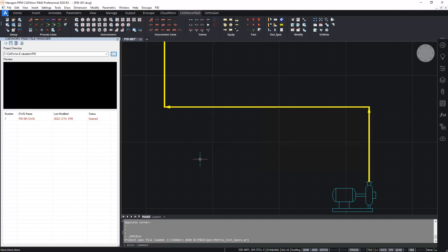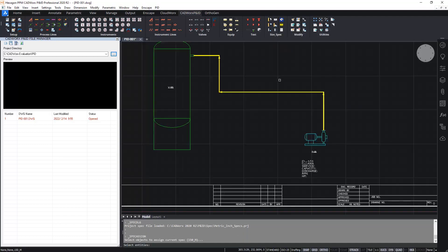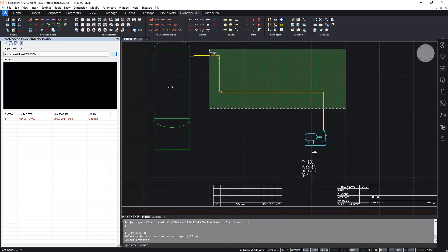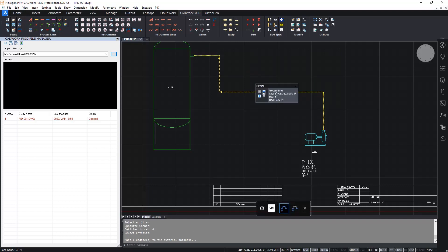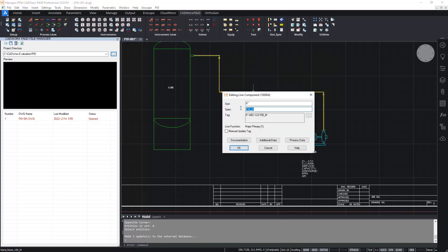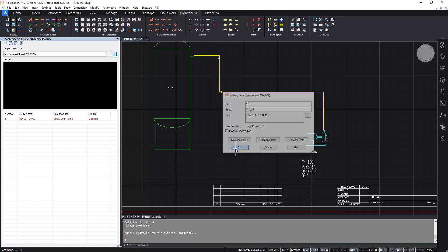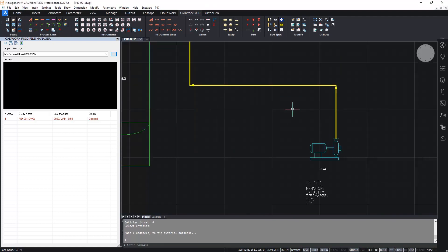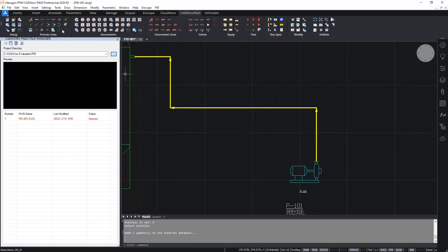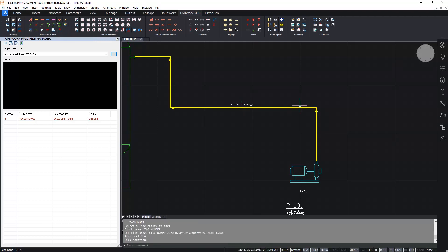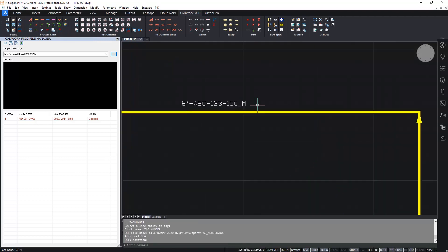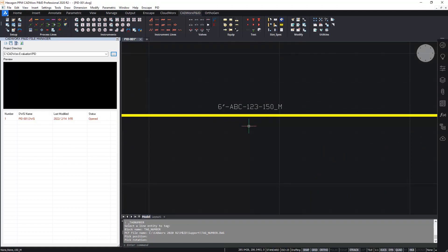Now, once that spec is set, I can then assign that to a selection of components. Of course, I only have the process line, but I'm going to assign that spec to the entire process line. Now, when I double click, we can see the spec has been assigned, the line number, the tag has been completed. And the final thing that I'm going to do here is I'm going to label that, annotate it onto the drawing by using this function here to tag the line and pick the line and select the orientation of the tag. Like so, the tag data is picked up from the selected process line.